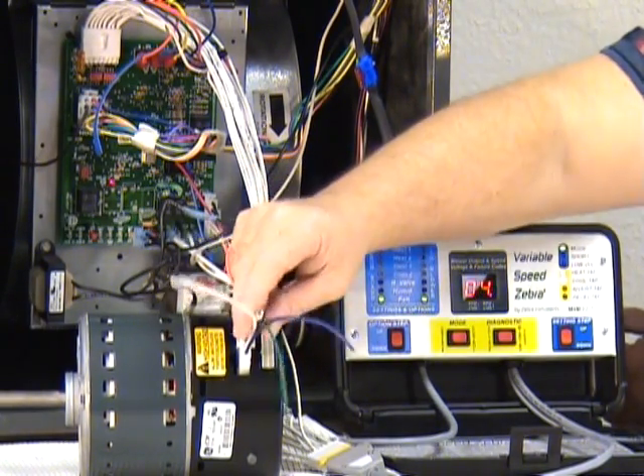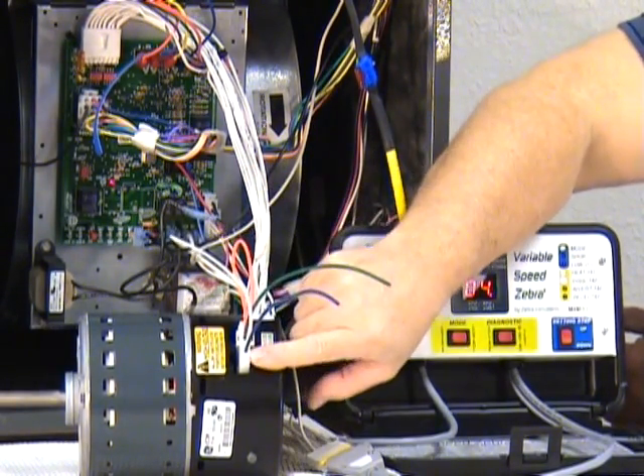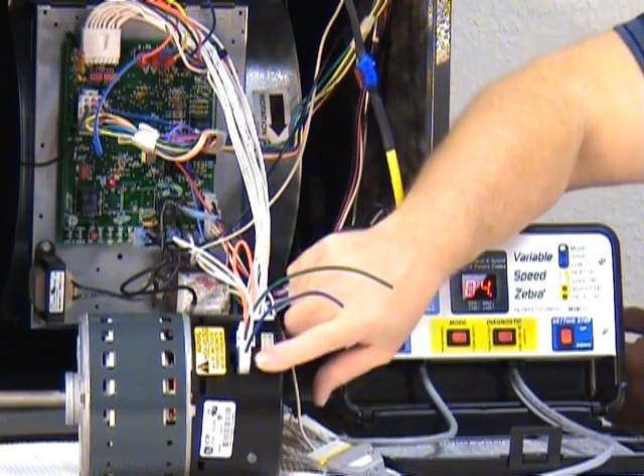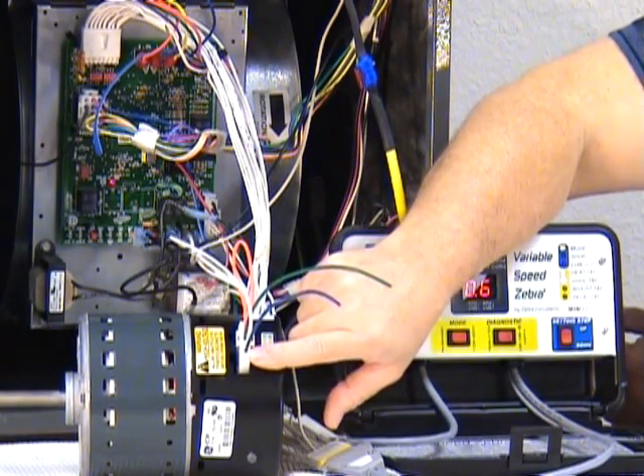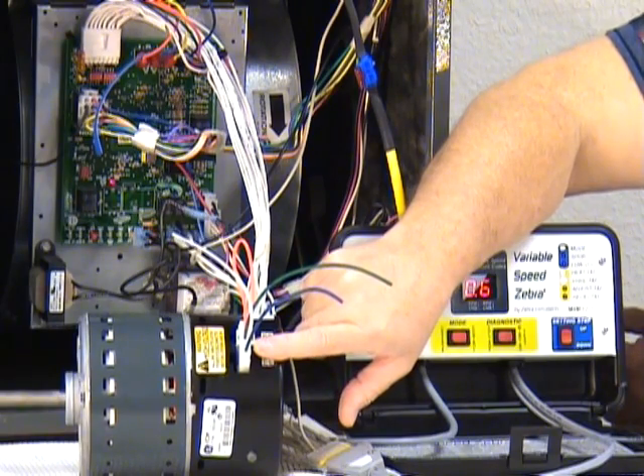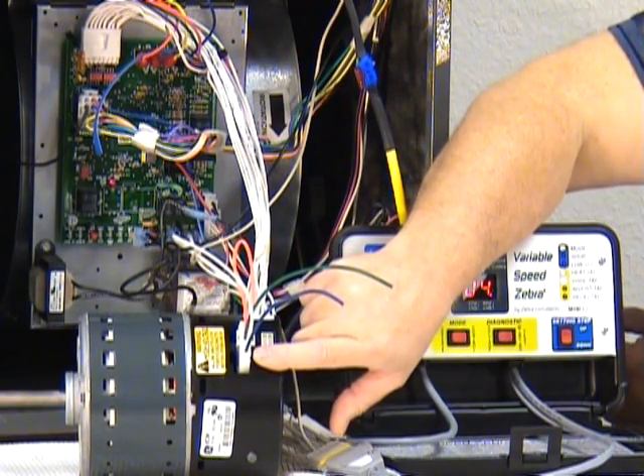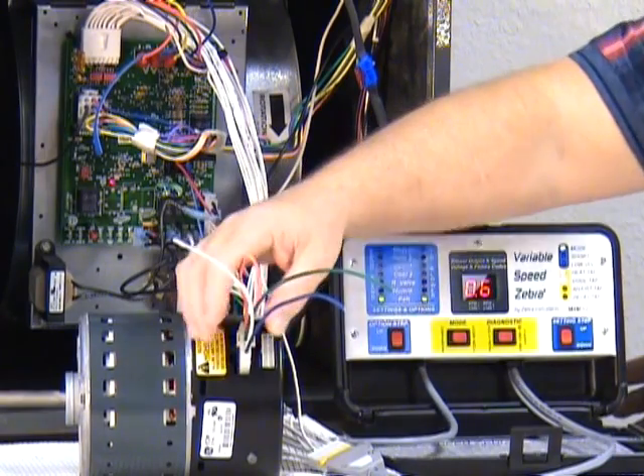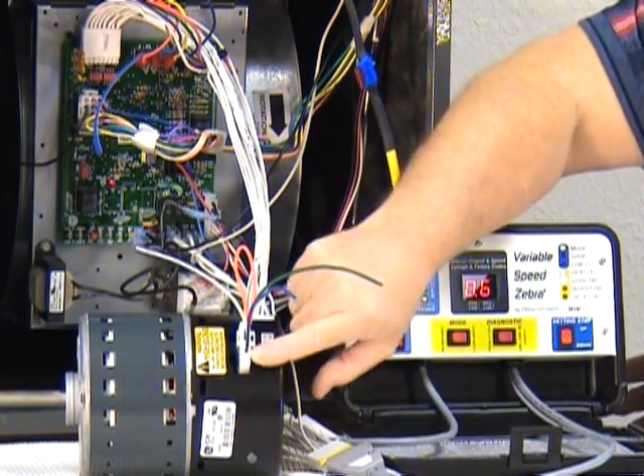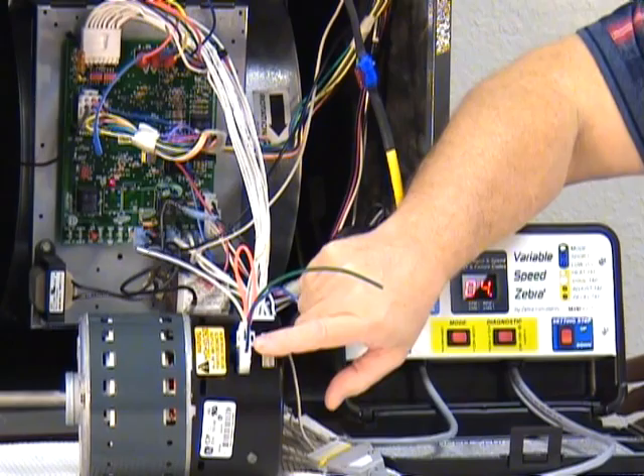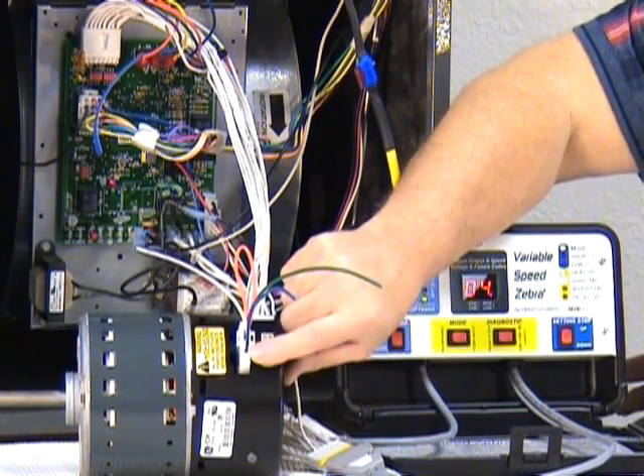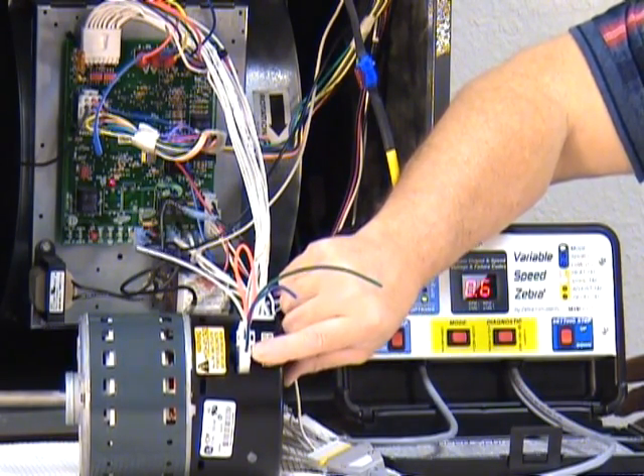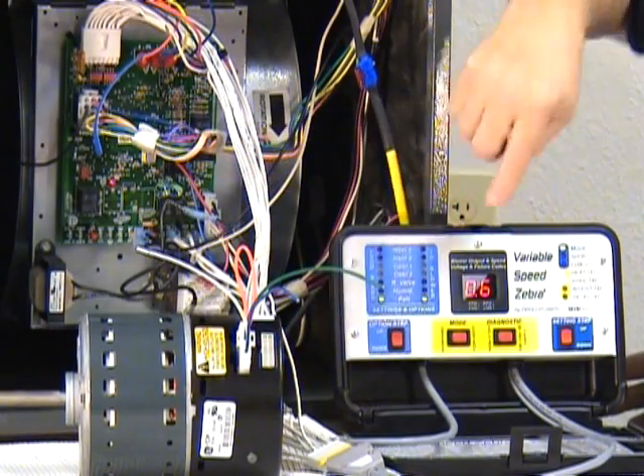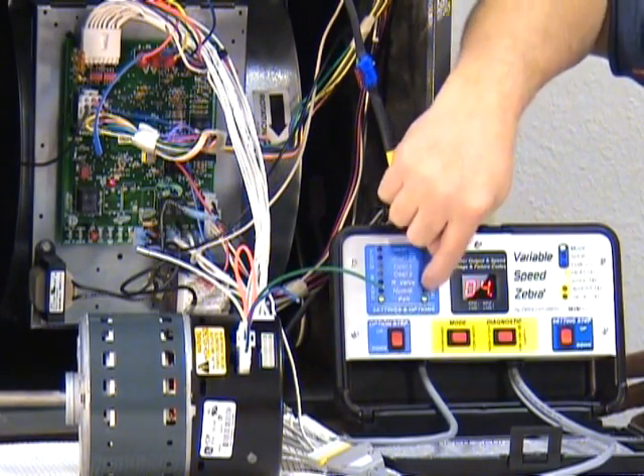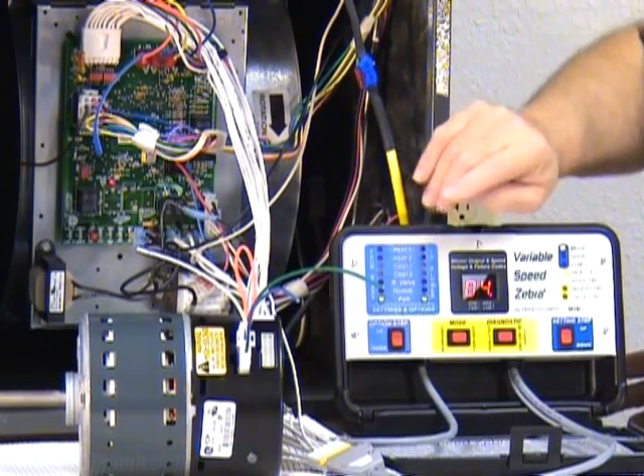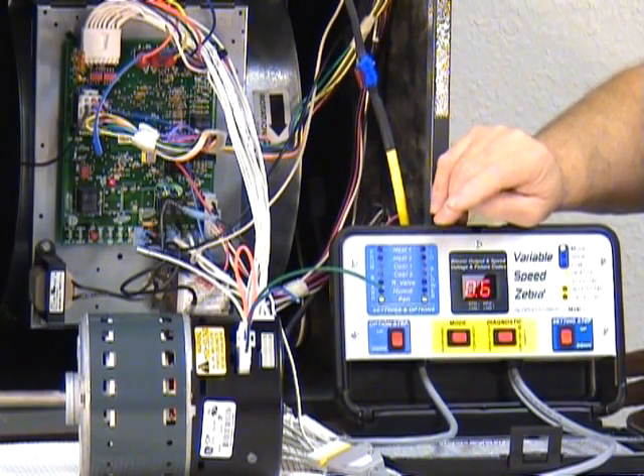Where you check your voltage on a motor is the first two pins that are away from this jumper side. The first one is the hot, the second one is the common if it's 110. If it's a 240 volt system, they're both hot. Gently put voltmeter leads, probes, touching the little contacts on those wires. If you see 240 volts or 120 volts across there as appropriate, and if this signal is sending out the signals to the motor on this side, you know you've got a problem somewhere in your motor.